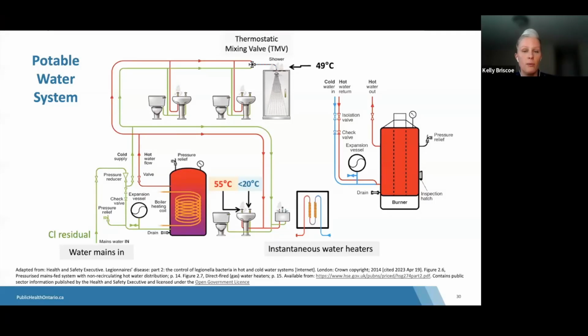So for settings with vulnerable populations, thermostatic mixing valves can be used to prevent scalding. Essentially, these valves blend cold and hot water together to get to an appropriate temperature at the point of use. It is important to consider that these valves can also provide favorable conditions for growth between the valve and the faucet or the tap. For this reason, the valves should be installed as close to the point of use as possible to minimize the storage of blended water. And cold water temperatures are recommended to be 20 degrees Celsius or below. However, as we previously noted, there are conditions throughout the system that can cause an increase in cold water temperatures, which would again allow for potential growth.